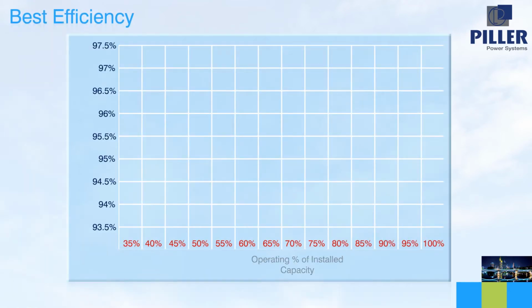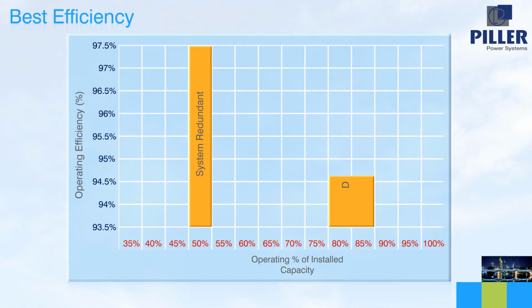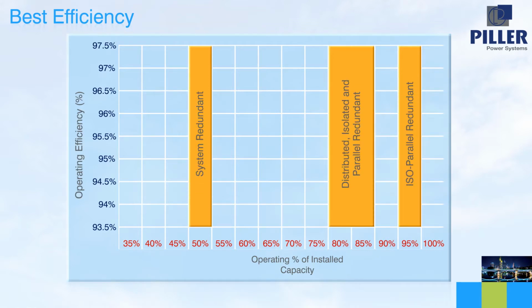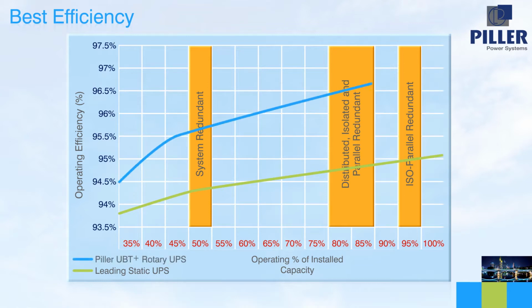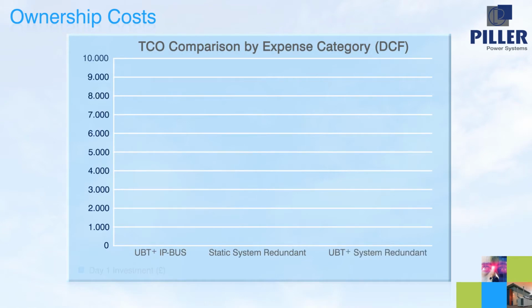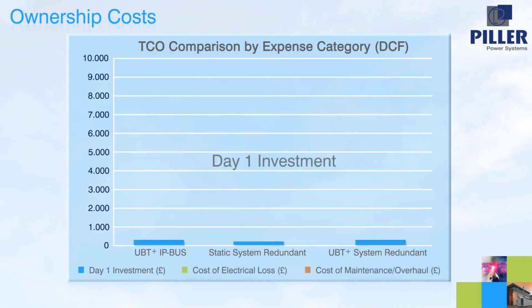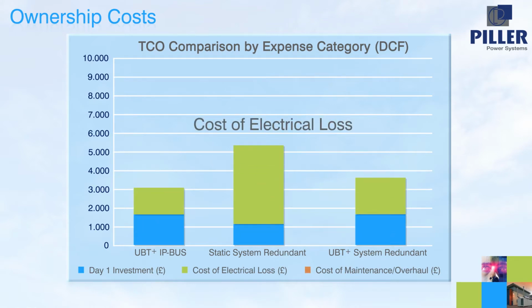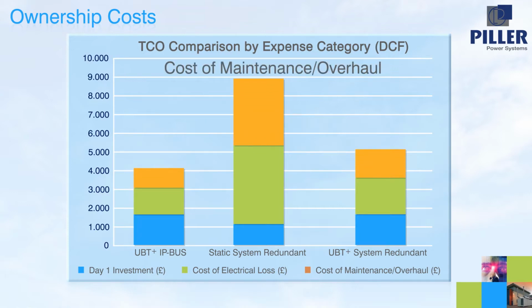The isolated parallel concept is the only solution that can offer a highly reliable, fault-tolerant, and concurrently maintainable system at the same time as delivering the highest electrical efficiency. This difference in efficiency, particularly at partial loads, brings about significant economic benefits for the data center user. When those efficiency gains are combined with the longer life and the reduced maintenance requirements of the rotary UPS, the total cost of ownership can be significantly better than other schemes and technologies. That's because the main cost factor over the life of the installation is electrical efficiency.